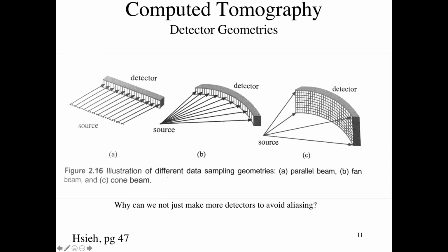And this is the way CT scanners were for probably 15, 20 years, right? They made a single arced row of detectors, usually about 1,000 detector elements, and a source, and then you would rotate that source around the patient and get different views on this detector element.